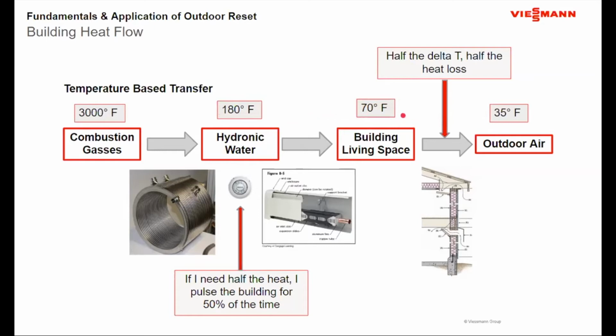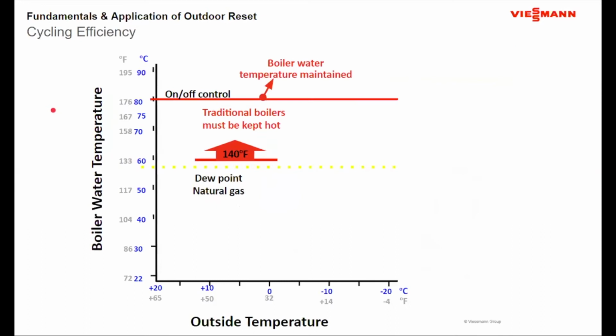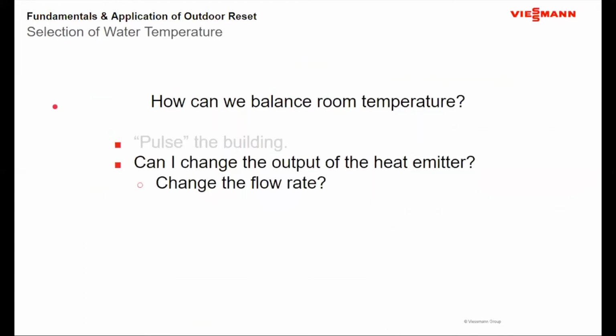Okay, the thing is, there is variation here in temperature, and I didn't do anything here. Nothing here improves because I'm still staying at the same temperatures. But from an aspect of simplicity, it's a very simple way to approach it, and it's one that's been used effectively for quite a number of years. A lot of times when somebody says, can we balance it better? The question always comes up, when I pulse the building, I'm looking at a fixed flow rate. Well, what about varying the flow rate? Can I change the output of the heat emitter by changing the flow rate through that heat emitter? Okay.